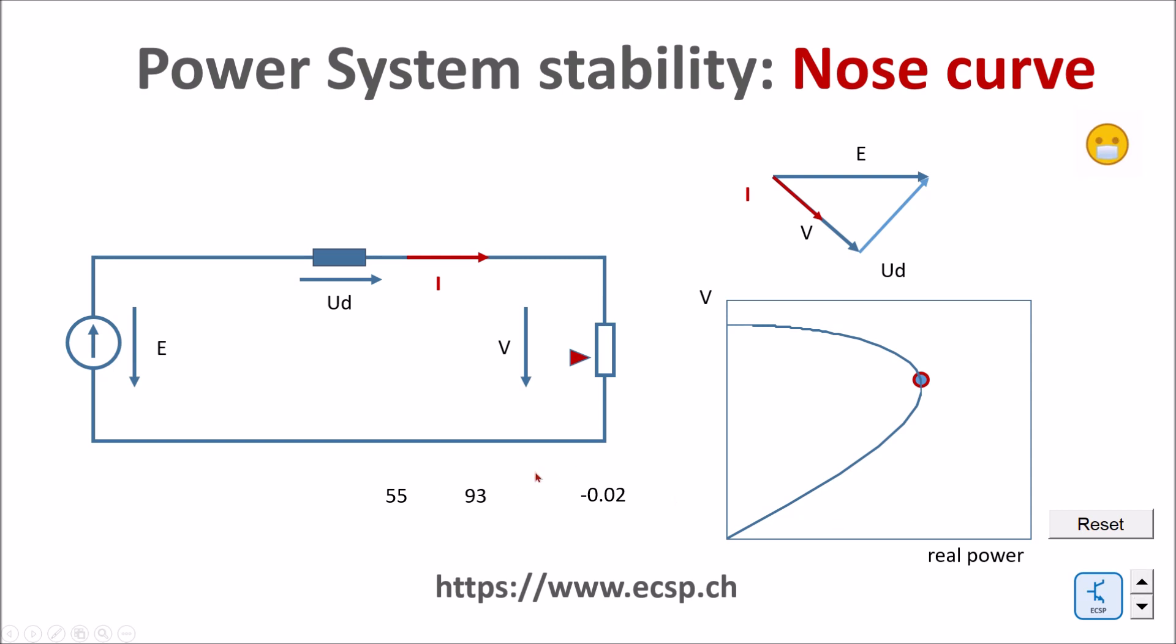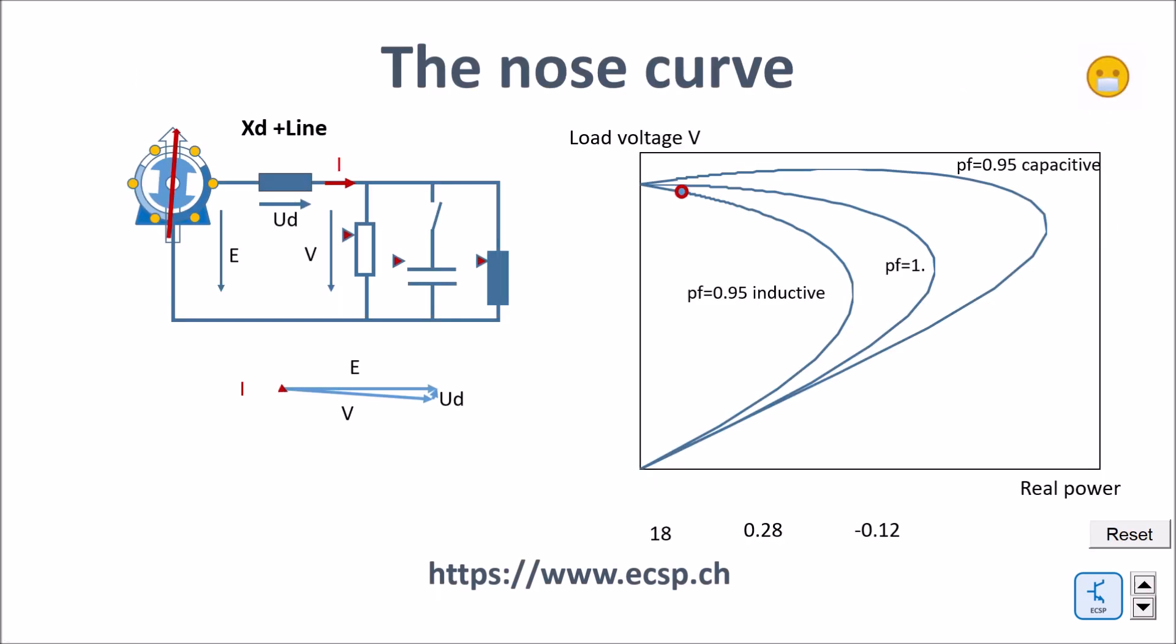The shape of the nose curve strongly depends on the cosine phi of the load. And also this point of no return will change accordingly. Here you can now see how the nose curve depends on the power factor of the load. We have here three cases. This is more an inductive load. And here we have, and you can see as soon as we cross this no return point at the edge of the curve, the voltage collapses, meaning that the generation loses grip.